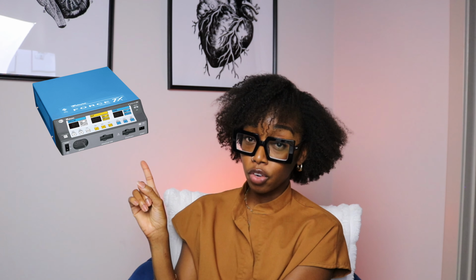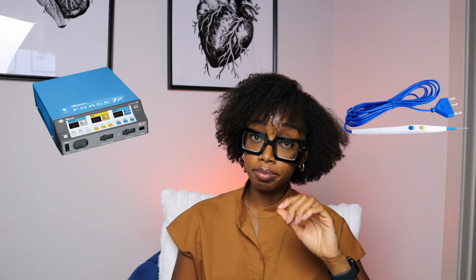So here's some basics. The generator creates the electrical energy. The active electrode, or the pencil, delivers it to the patient. And then the patient return electrode, aka the grounding pad, which sticks to the patient, safely returns the energy back to the generator. As a surgical tech, you want to make sure you're checking that the grounding pad is properly placed on well vascularized tissue. Now, the nurse or circulator does that, but it does not hurt for us to keep eyes on that as well. You also want to confirm that the ESU settings are correct for the procedure, so make sure it's not on 100 and 100. And never let the active electrode or the pencil rest on the patient or the drapes. Don't do it, because electrical safety protects everyone, definitely the patient, but also you. And we don't want no fires. We don't want any fires, baby.